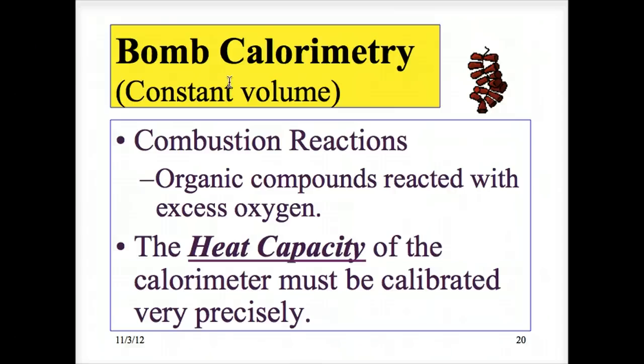So these are different calculations. These are actually very easy calculations, and what I'm worried about basically is the rating of what they call the heat capacity. The heat capacity for your bomb will be in joules or kilojoules, I'll say kilojoules, per degree. Note that there is no gram. It doesn't matter what the gram is. We're dealing with the actual instrument itself. I'm going to leave it like that, and I think it should be clear when we hit a couple of sample problems coming up.